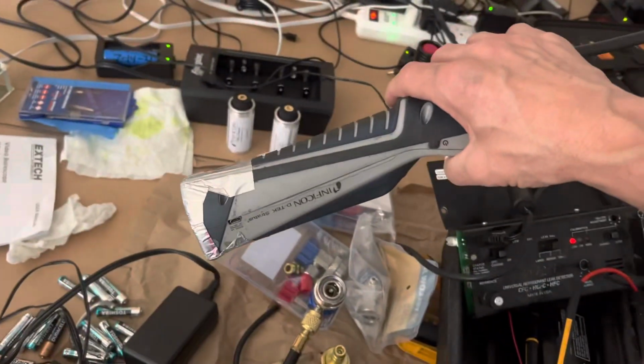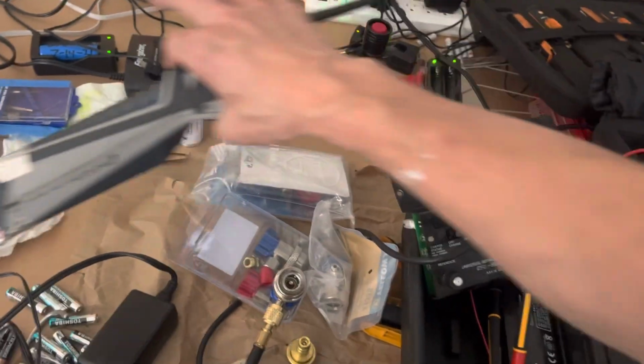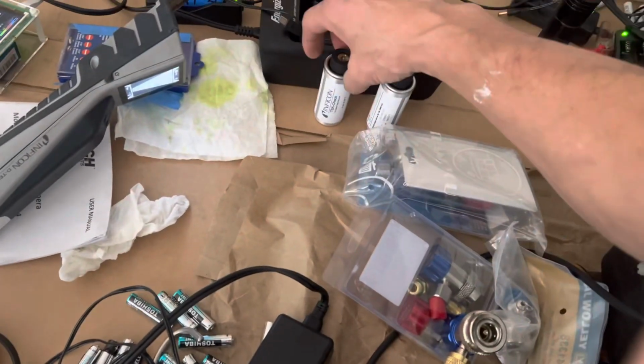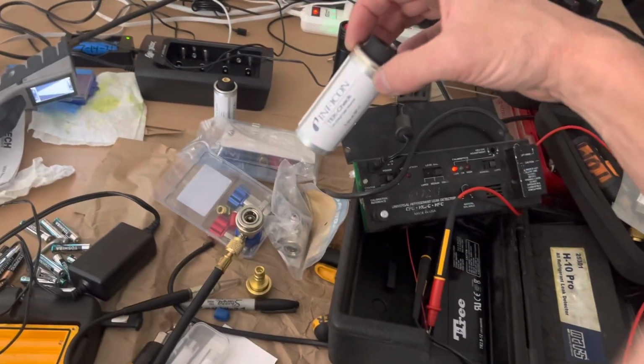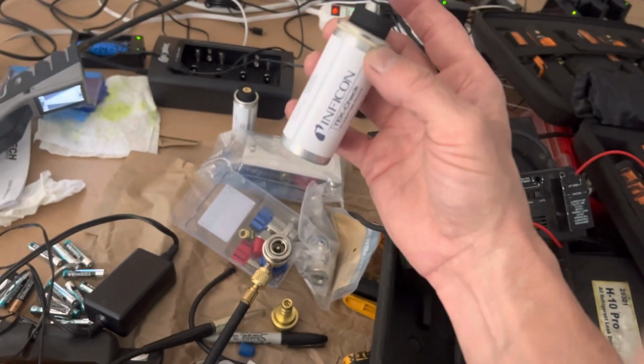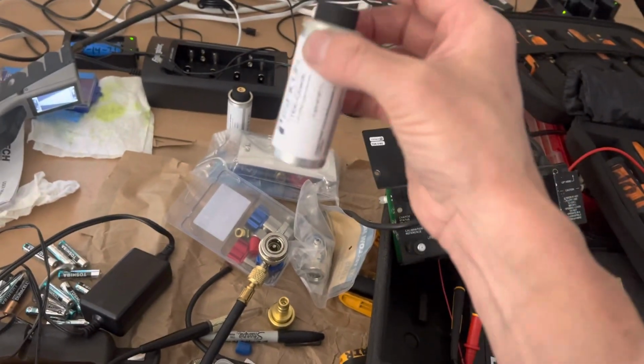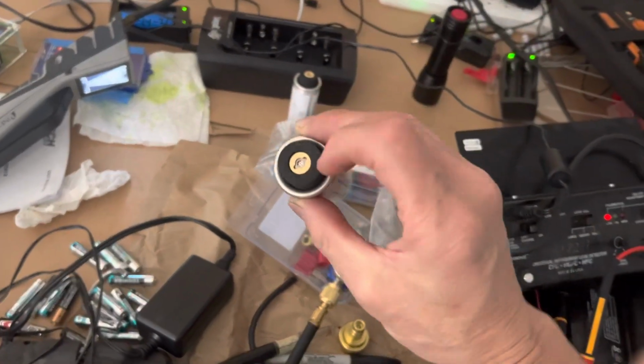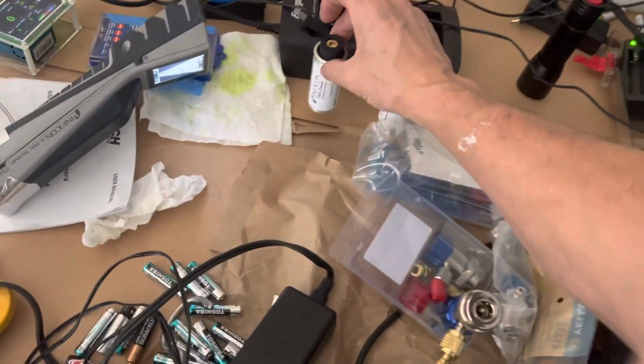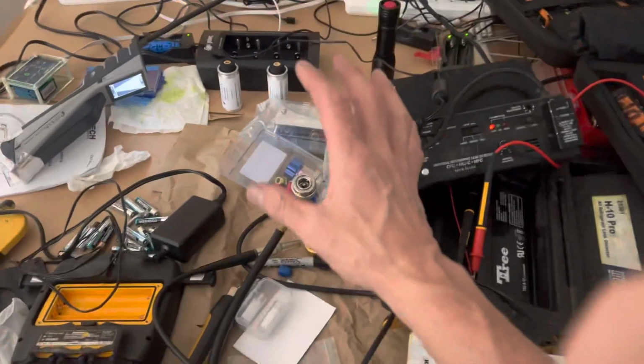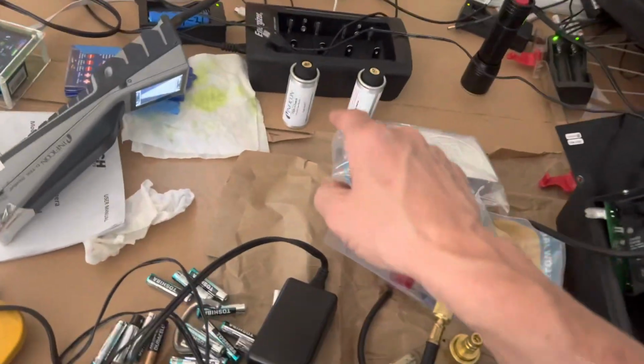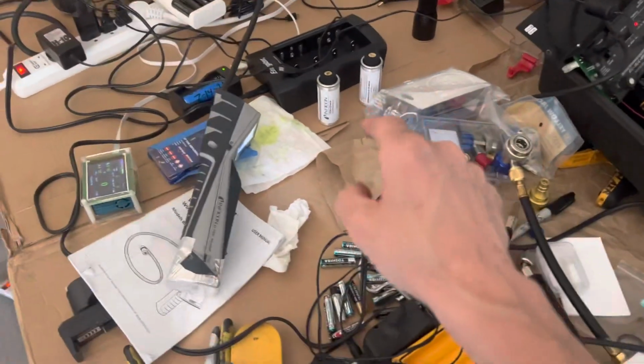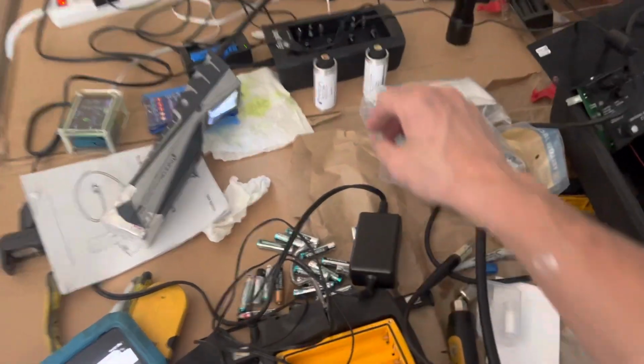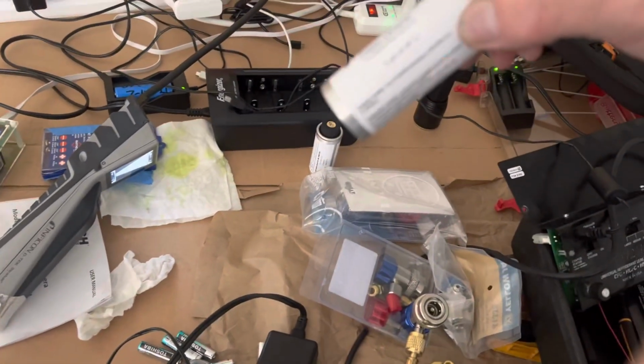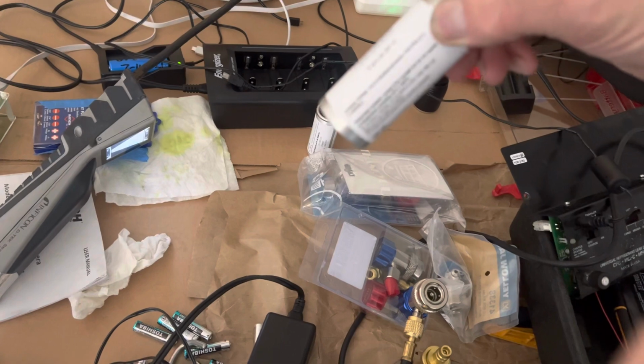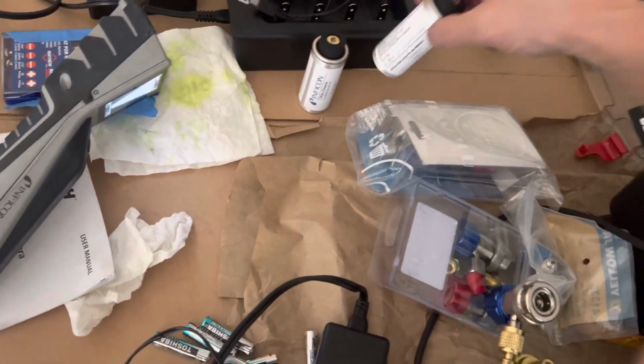Inficon is the manufacturer of the Stratus Detect that I have here in my hand. You can purchase these, of course, separately. These are calibrated vials that contain refrigerant, about 5 grams in them. They have a calibrated leak at the end. At 70 degrees, I think 70 or 72 degrees was their rated calibration temperature, they leak an absolutely minute amount of refrigerant. I can't even remember the spec.